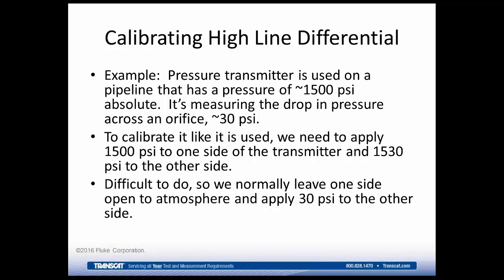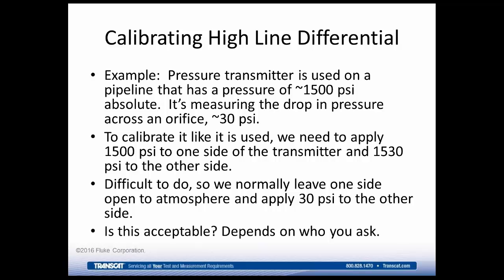So it's commonplace to normally leave one side open to atmosphere and apply 30 psi to the other side. So there, you're still measuring the same differential. A differential style device will always have two test ports, a high and a low. The pressure on the high side is 30 psi greater than the low side. The difference being that when it's actually used, it's still 30 psi different, but the low side is 1500 and the high side is 1530. Here, it's 30 psi, it's 0 or atmosphere on one side, and 30 psi higher on the other. Is it okay to do that? It depends on who you ask, but in most applications it is acceptable.